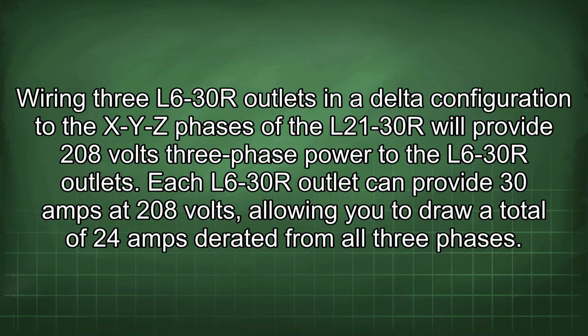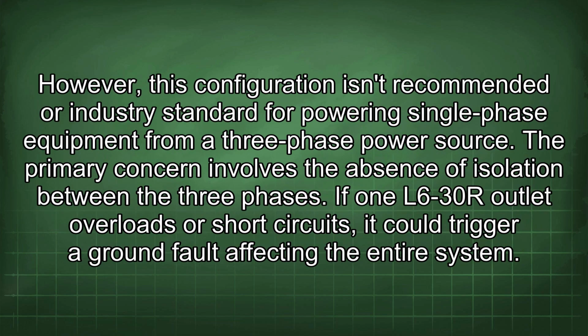Wiring 3 L6-30R outlets in a delta configuration to the XYZ phases of the L21-30R will provide 208 volts 3-phase power to the L6-30R outlets. Each L6-30R outlet can provide 30 amps at 208 volts, allowing you to draw a total of 24 amps derated from all three phases.